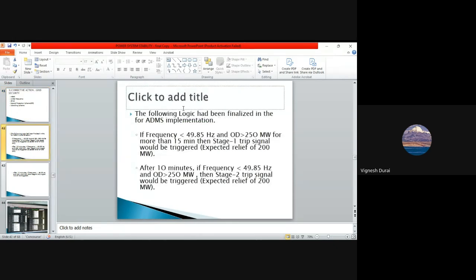The following logic has been finalized for implementing ADMS. See, we have already seen the contingency. Your grid frequency should be within 49.5 to 50.3. That is a standard thing. But even before that, we are securing the system. If the frequency is below 49.85, or your overdrawal, which I said earlier, means that your load is more than your generation by 250 megawatt. This applies only to our state.